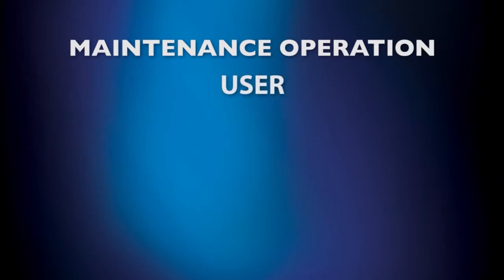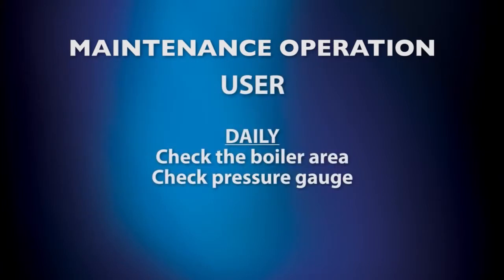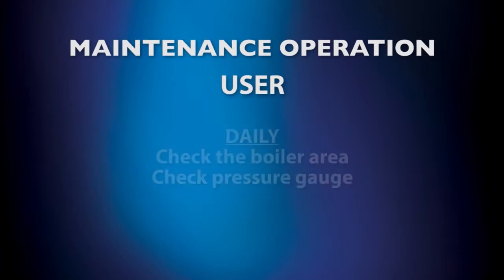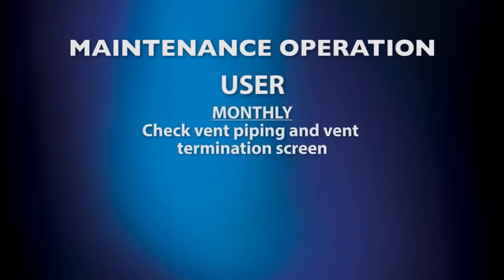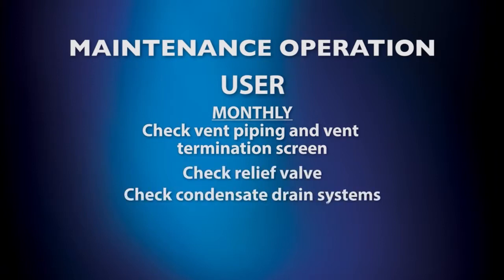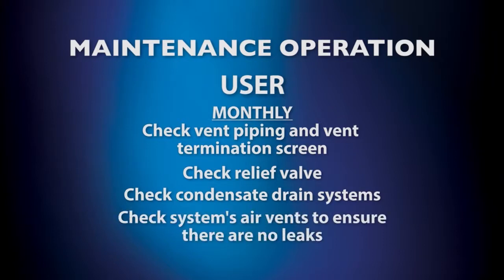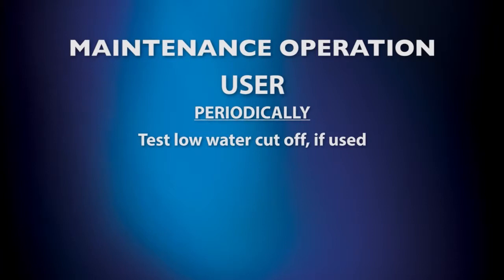For the user, the following maintenance operations must be checked. Check the boiler area and pressure gauge daily. Monthly, check the vent piping and vent termination screen. Check the relief valve. Check the condensate drain systems. Check the system's air vents to ensure there are no leaks. Periodically, test the low water cutoff, if used. And reset the low water cutoff, if used.